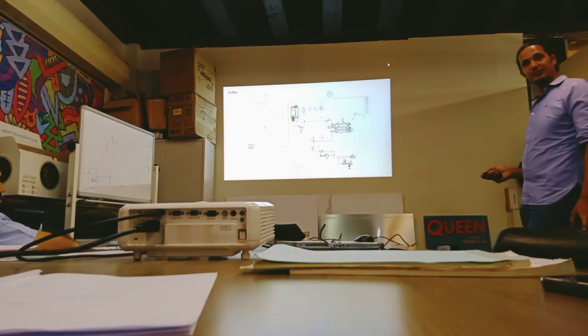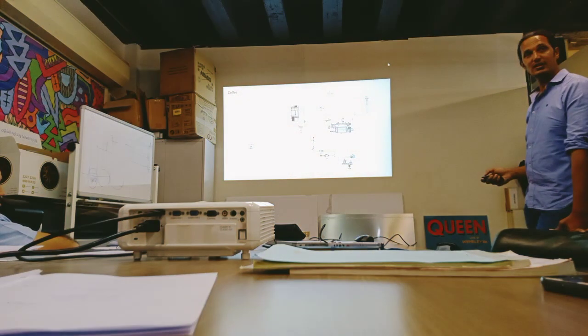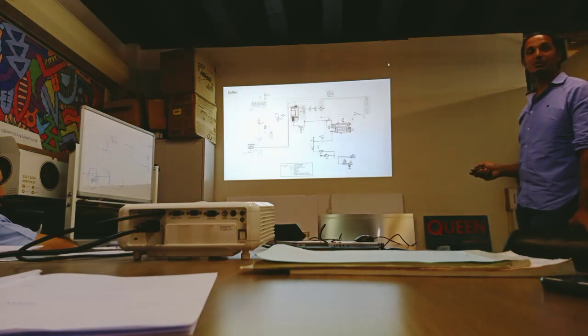So, VE is the expansion valve. It's also set, I think, at 12 bar. So if there is any high pressure, it will release out from the expansion valve. After the expansion valve, the water takes direction to the boiler or to the heat exchanger. Always separate the area outside the heat exchanger and inside the heat exchanger. Outside the heat exchanger, it can resist a maximum of 2 bar pressure. Inside the heat exchanger, or this coffee circuit, it can resist a maximum of 12 bar pressure. Okay, do not mix. Always separate these 2 lines.